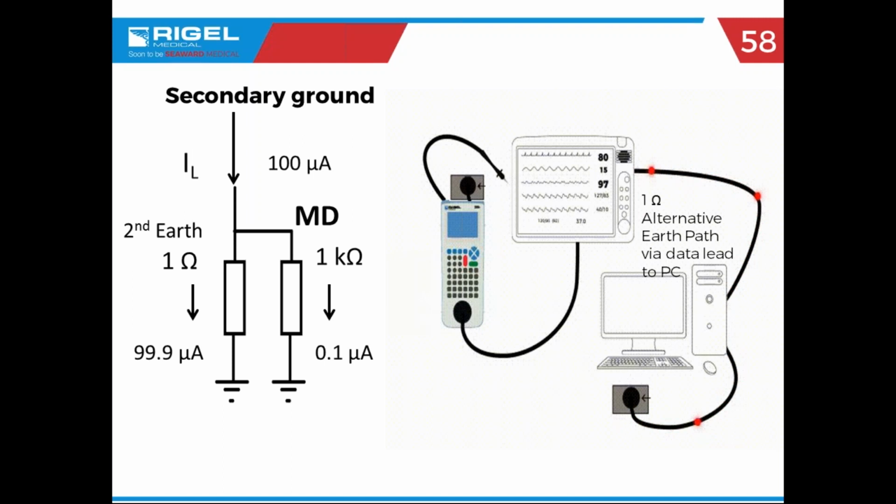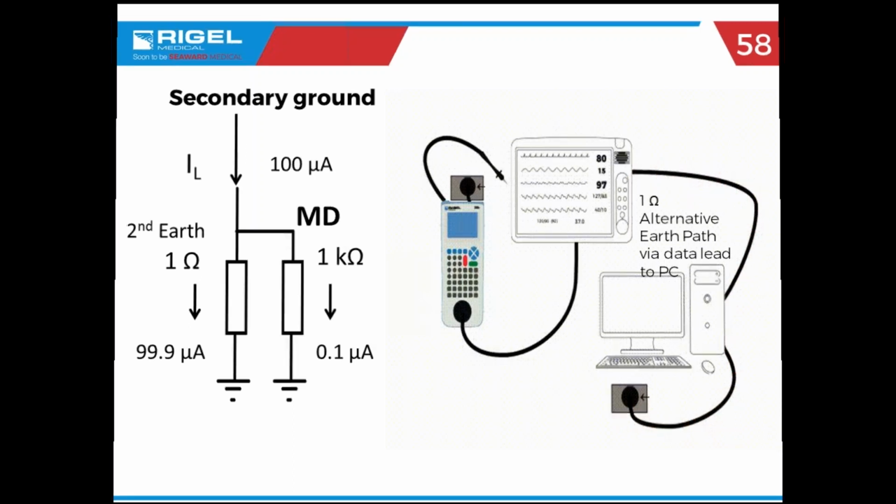Fortunately, safety analyzers will, some, I'm not saying whose, but we are sponsoring this webinar. Anyway, safety analyzers will come up and give you a message to check for a secondary ground condition to make sure that you're getting a good accurate reading.